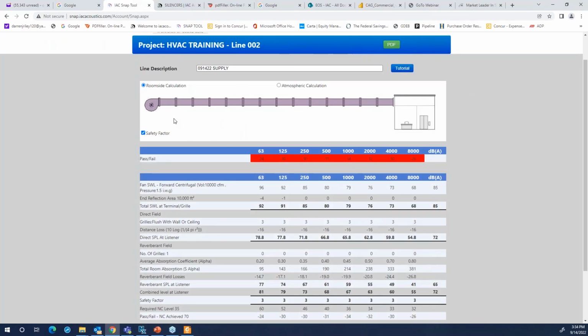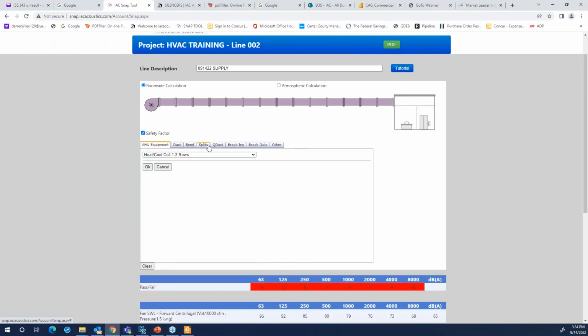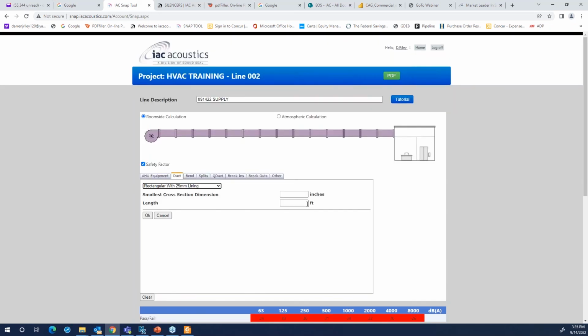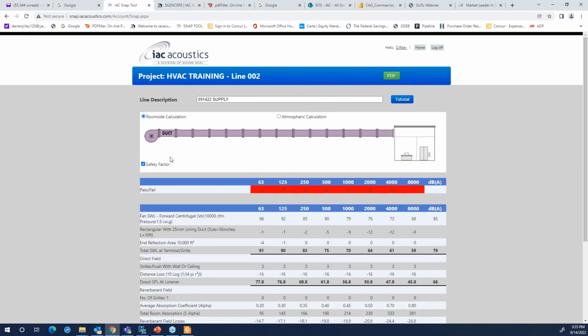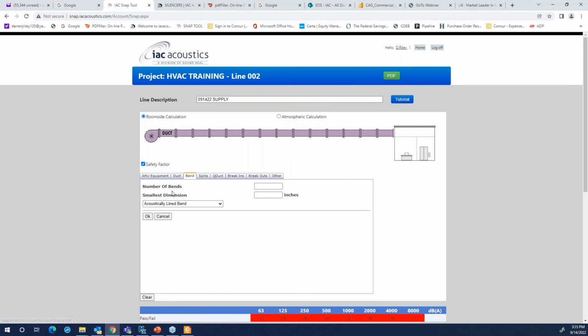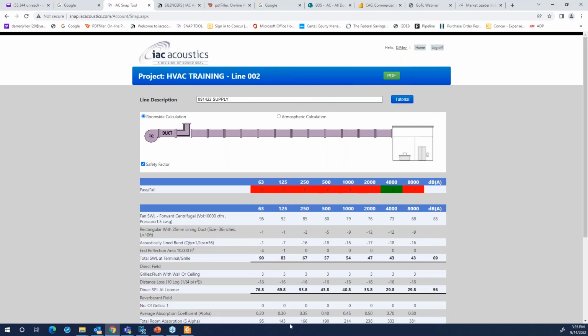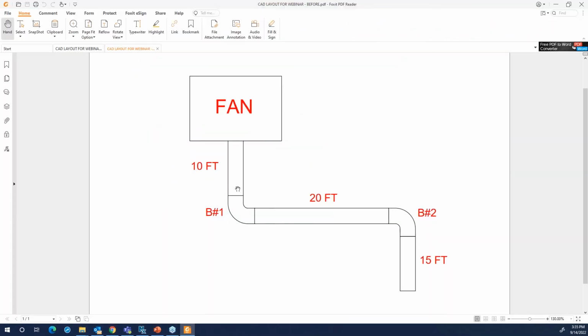So I'm going to go ahead and put in my ductwork. You have a couple of different things here you can use: remember, Q ducts, quiet ducts, and our bends. Today we're going to focus on these three. If you want to focus on splits, break-ins, breakouts, again, email me. We can go over those together one-on-one. For ductwork, typically it's going to be the 25 millimeter lining. Again, the smallest cross section is what you're going to enter in, meaning, again, a conservative approach. We have 10 feet of duct. We then have a bend. Number of bends is 1. Smallest dimension is 36. So what we have right now is this section right here.